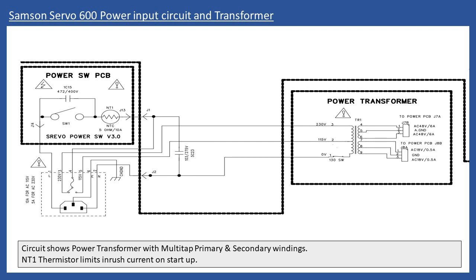And it's not easy, but sometimes you could catch the slide switch and it inadvertently moves across, and then you've reselected a lower voltage. If you apply 230 volts maybe to a transformer which is rated for 115 volt supply, what will happen is the transformer will heat up, and then you'll hear almost like an audible crackling sound as the transformer gets too hot.